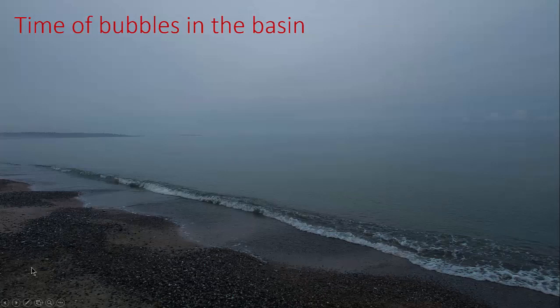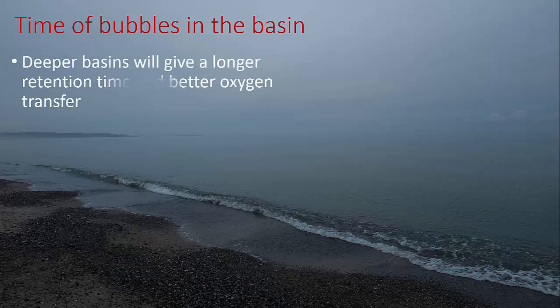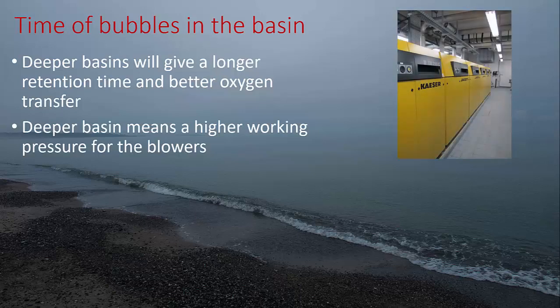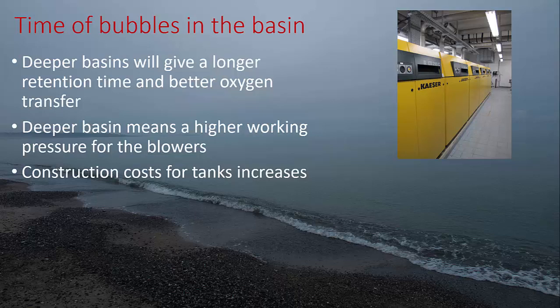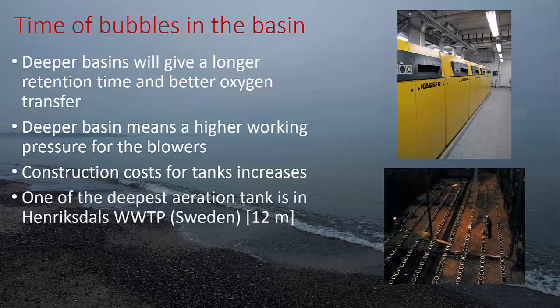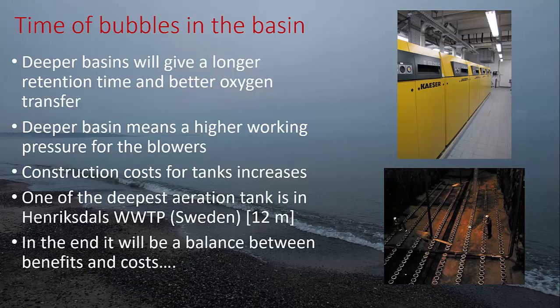What affects the time of the bubbles in the basin? Basically, the longer the bubble stays in the basin, the better the oxygen transfer. Deeper basins give a longer retention time and better oxygen transfer, but deeper basins also mean higher working pressures for the blowers, and construction costs for deeper tanks will increase. One of the deepest aeration tanks is at Henriksdal in Sweden, which is about 12 meters deep. In the end, you need a balance between the benefits and costs of the deeper tank and the better oxygen transfer.